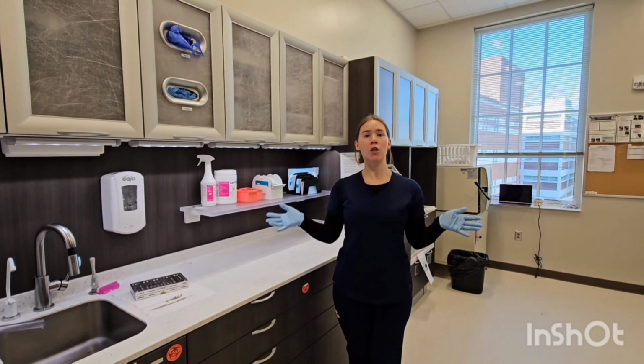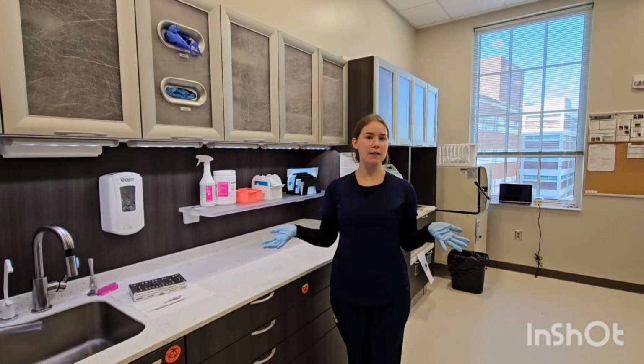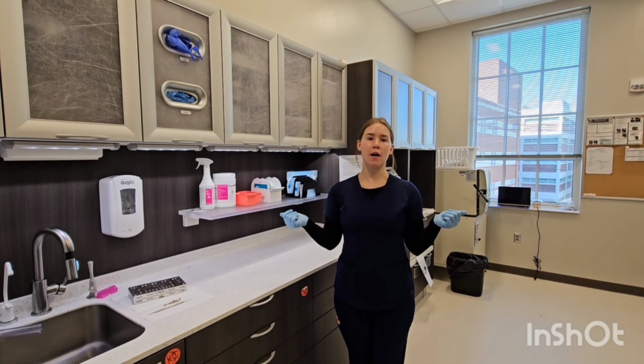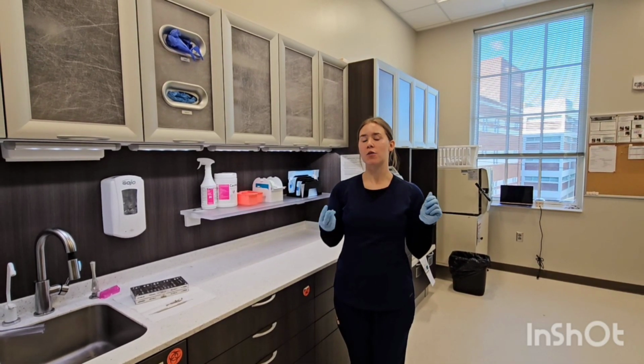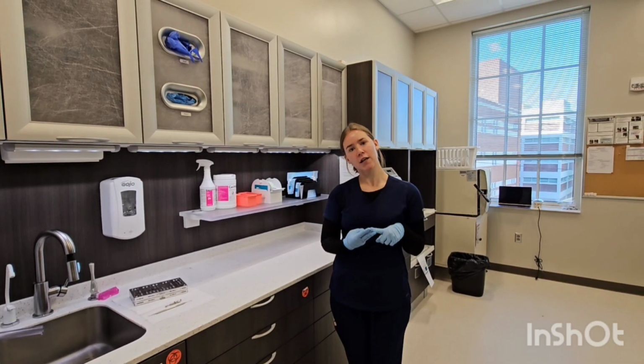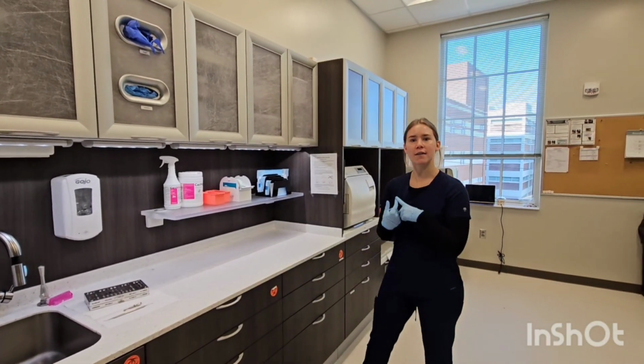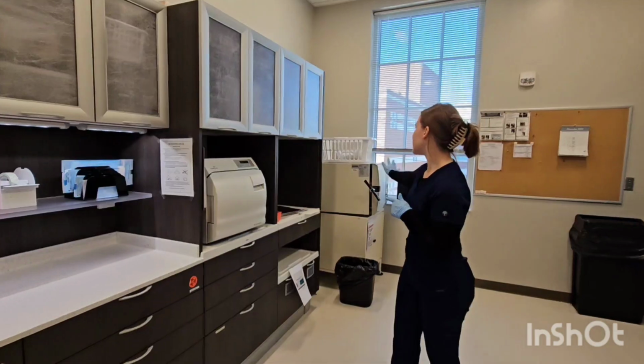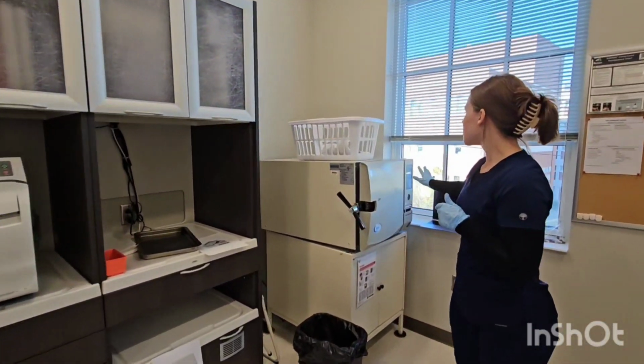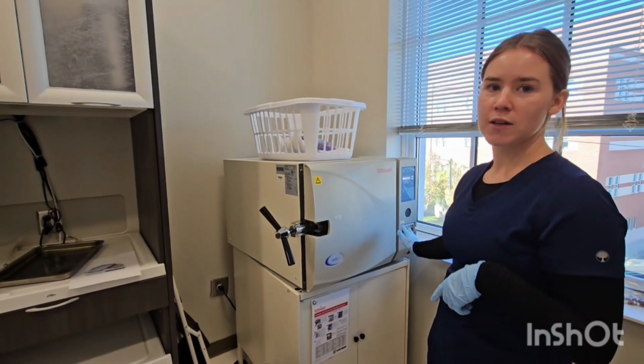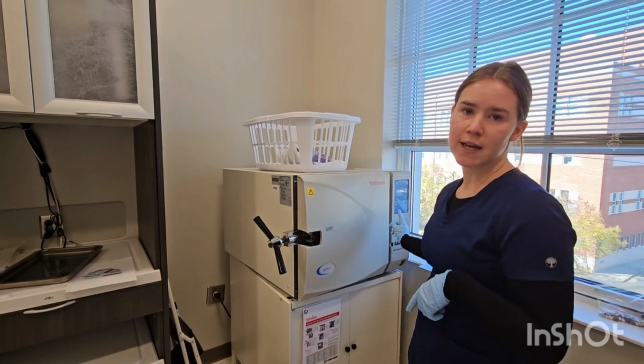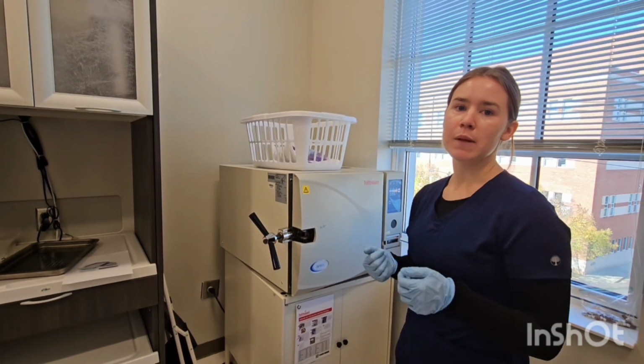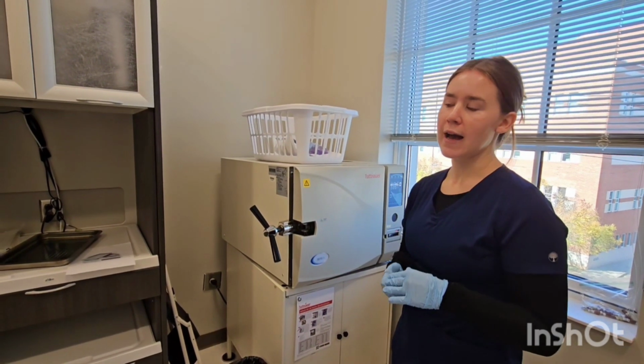So to ensure that everything is sterilized in the sterilizer, we use sterilization monitoring. There are 3 different types of sterilization monitoring. The first is physical monitoring. We're going to look at the physical sterilizer and check the different monitors on the sterilizer, such as the temperature indicators, to make sure the conditions have been met for everything to be sterilized.